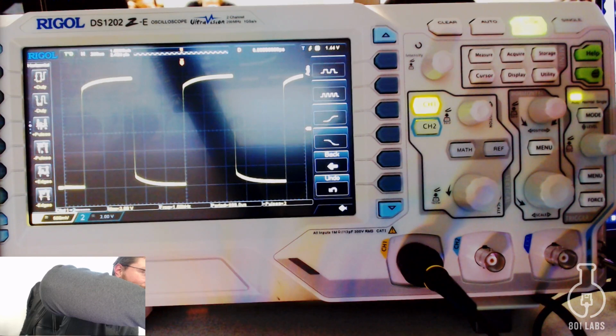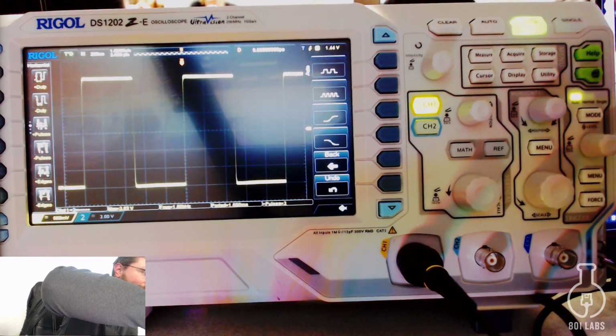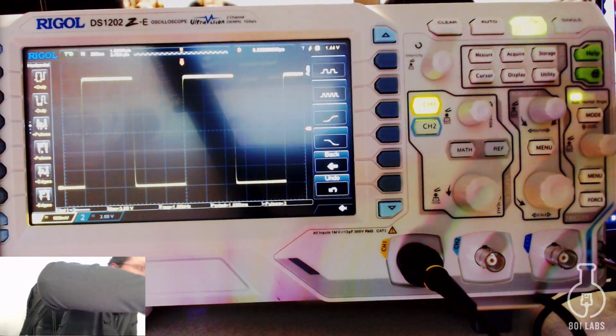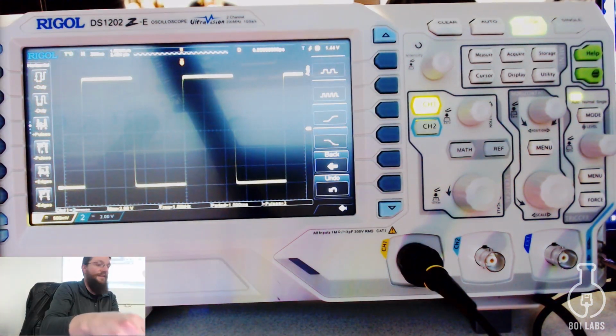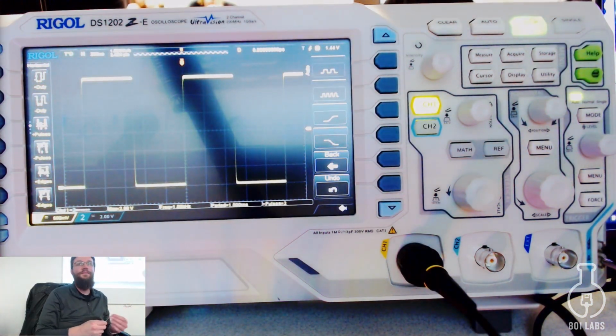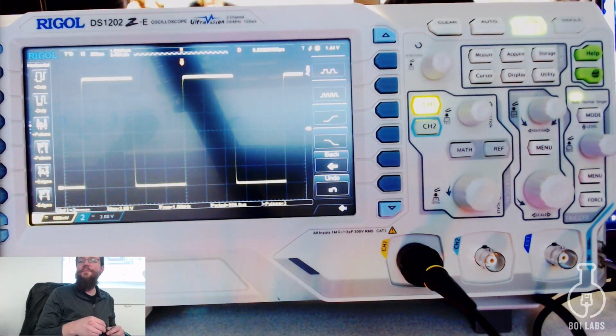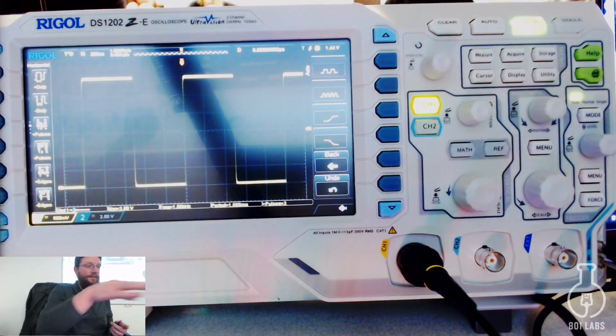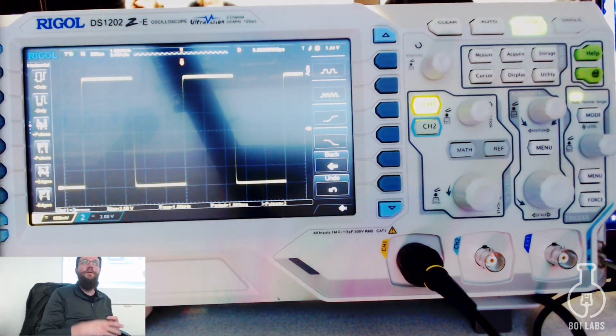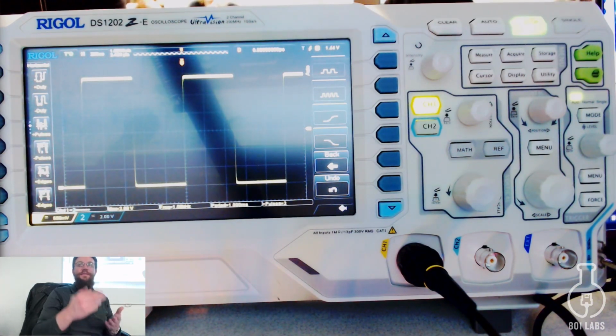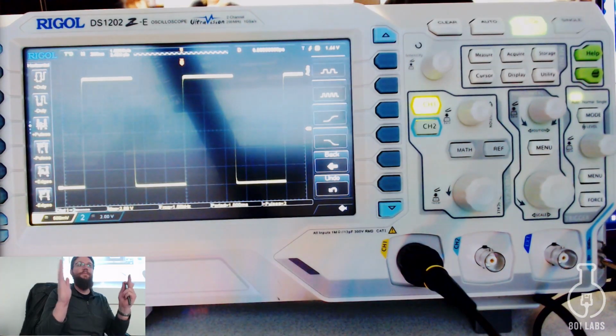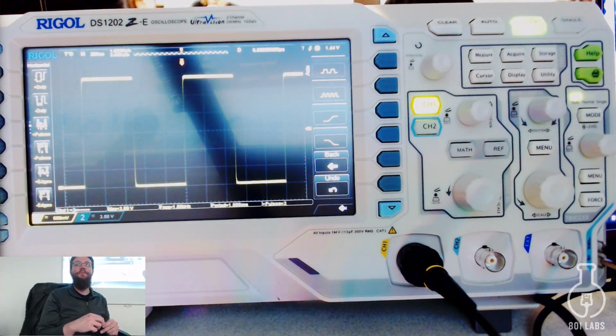Yeah, so there you can see if it's turned down too far, the corners drop out, and if you go up, the corners go too high. What are you turning? There's a little screw inside the probe itself that adjusts the capacitance of the probes. So on mine, it's right here. So you can have multiple tunes for different applications? Yeah, well, it's usually per scope. Okay. So you tune your probe to your scope and then not use it on other things. Makes sense, because there's little variations in each scope. Yeah, it's like when you buy a capacitor and they're plus or minus N%. So rather than spend $100 on a super precise capacitor, you add a variable to the system that you can adjust. Yeah, that makes a lot of sense.